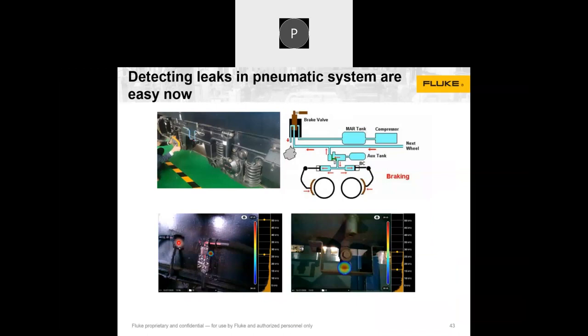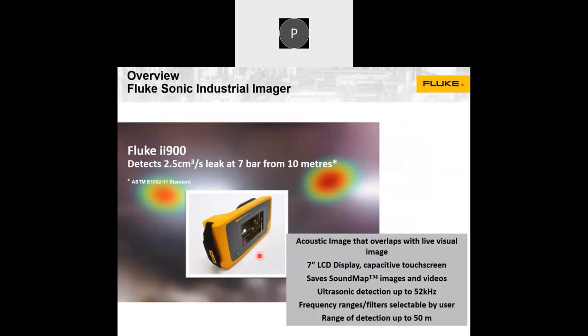It's just like a thermal imager screen. This is the instrument, and this is the way it detects the leaks, pinpointing the exact spot where the leak is coming from. So it's easy to detect leaks, or even partial discharge the same way. This device, we call it an acoustic imager or sonic imager, and it comes with 64 acoustic sensors and a camera, so from the entire field of view it captures those sound waves and shows in a visual image where they are coming from. That is how it helps you find the leaks.